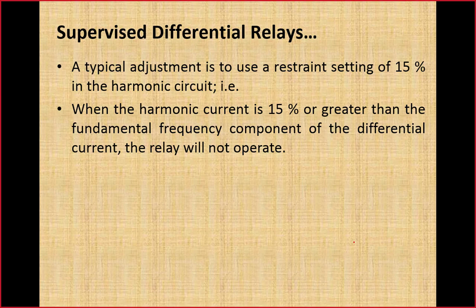It means that if the harmonic content present in the current is less than 15% or nothing, only then will the relay operate. Otherwise the harmonic contents are going to block the operation of the differential relay, because the presence of harmonic components in the differential current is an indication that this current is due to inrush from energization, inrush due to fault removal, inrush due to overexcitation, a sympathetic inrush current, or CT saturation. So relay operation will be blocked.